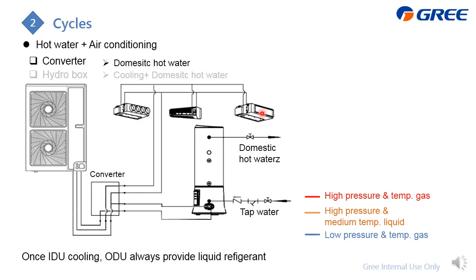First is the domestic hot water, and we need to send the hot gas, which is from the outdoor unit, and from here we just convert or change the direction, just follow this one to the water tank. Then after releasing heat, the hot gas will become liquid. Then we need to collect this liquid back to the outdoor unit, just like this. So in summary, to heat up this DHW, we need to release heat only from here, right?